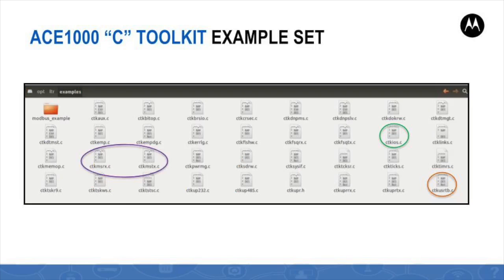A set of examples of C programs is provided under the virtual machine file system. These illustrate the use of most of the C system services or functions available to the application developer. The examples may serve the programmer as a basis for developing his unique application. For instance, the CTK-IOS.C example file demonstrates the toolkit APIs to read and write physical IO values. The CTK-MS-RX.C and the CTK-MS-TX.C example files demonstrate the toolkit's RTU to RTU communication APIs.